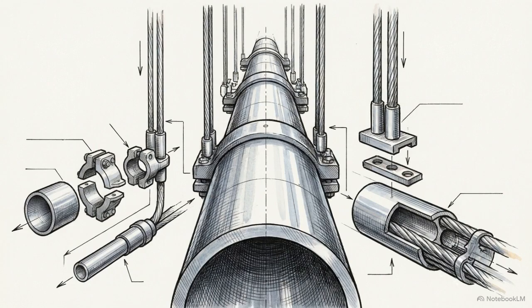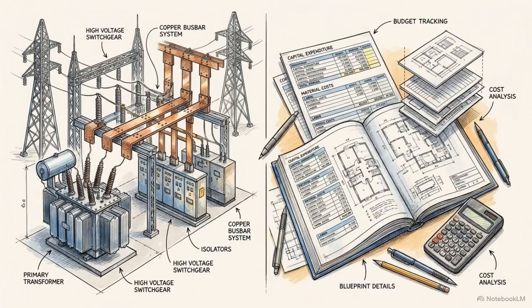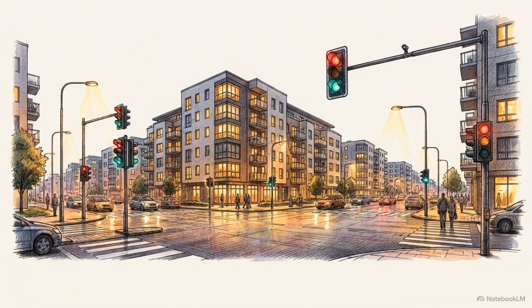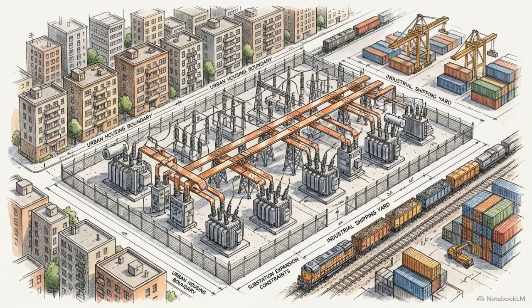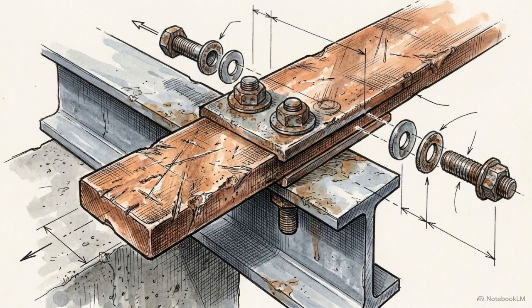This is the conductive nerve center, a heavy metal spine where all incoming and outgoing electrical currents physically meet. Designing these convergence points requires solving a harsh engineering tension. A busbar must operate with near-perfect reliability to keep the grid stable, but its construction is bound by strict economic and spatial constraints. That requirement for reliability is tested constantly because these exposed metal structures are inherently vulnerable.